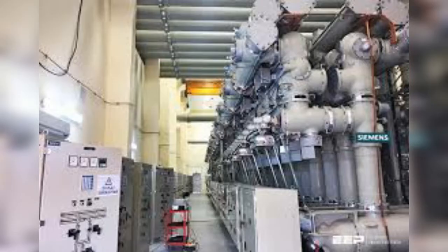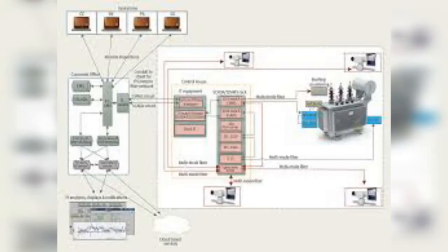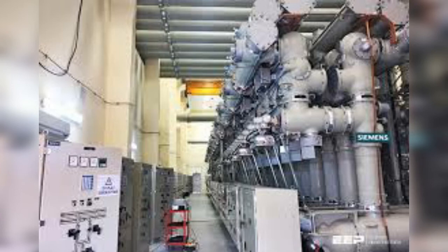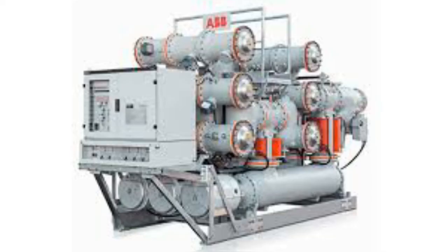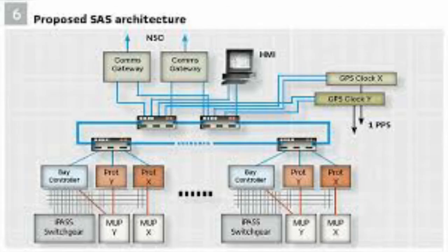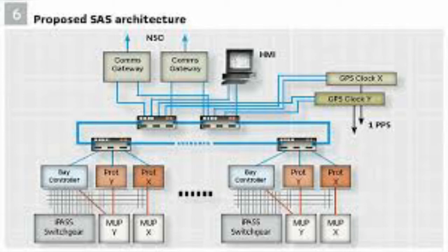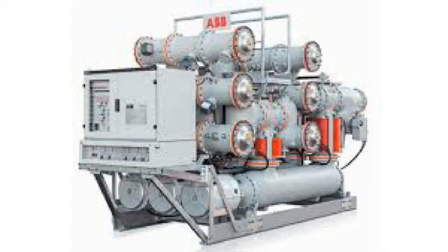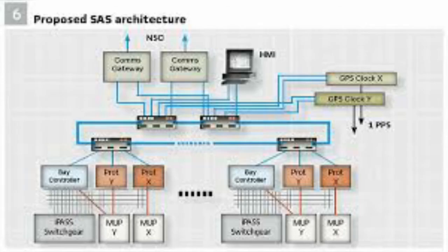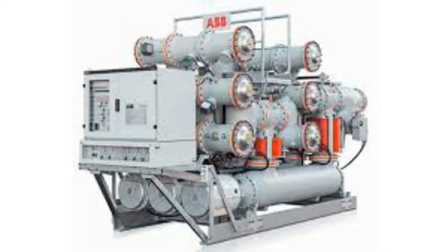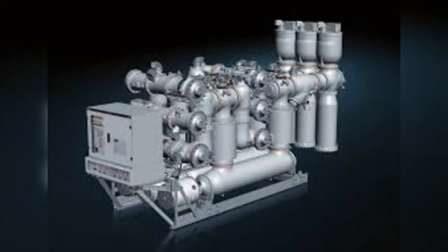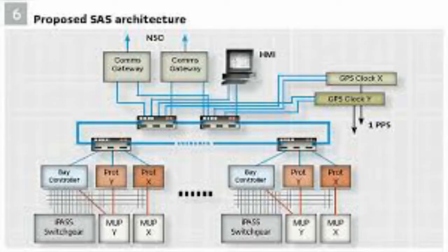All cubicles and other enclosures must be dust, damp and vermin protected. All cable connections must be arranged to the switch cables, which are also raised to the switchgear from a cable trench or running along the rear. All control cables must be separated from power cables. Before the specification of any switchgear, a trench distance is needed in a substation, and also the 11 kV switches, the power wiring and the protection wiring have different usages, so they need to be away from each other.